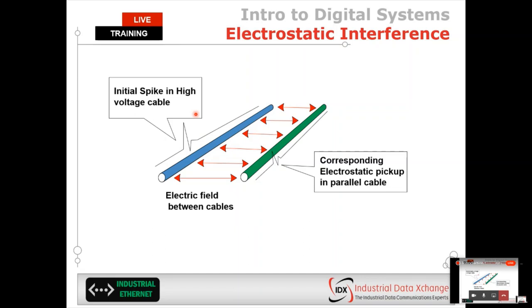This actually causes interference when it's run in close proximity to industrial Ethernet cable. The easiest way to protect from electrostatic interference is simply to provide a separation distance between your high voltage cabling and your industrial communication infrastructure.